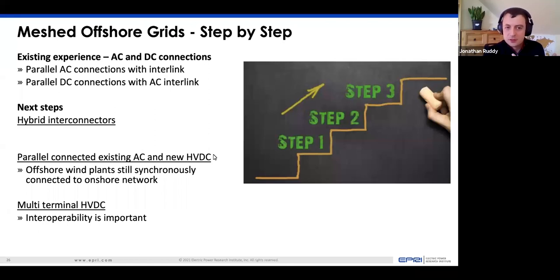I think the next steps to that could be things like hybrid interconnectors, where from one market area we have a connection out to a cluster of offshore wind plants, and another connection back to shore to another market area. And that path could not only be used for exporting offshore wind power, it could also be used as a path to transfer power between the two market areas. So kind of getting double the use out of the cable. And there's an example of that in Europe at the moment called Kriegers Flak, that's been developed between Denmark and Germany, where they utilize the spare space on the cable as a transmission path between the two countries.